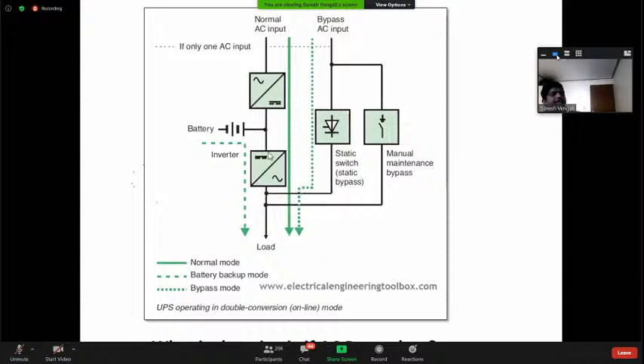So this is the inverter, and this is your static switch. The main purpose of this static switch is, if you lose this one, and it is saying this, if it becomes available again it comes back to here. So you are saying this is very reliable, and you don't want to lose supply for even one second. So for such high speed, you need a special electronic switch to change from normal to bypass to normal.